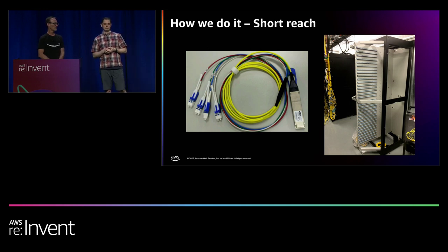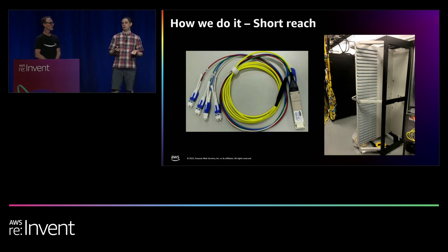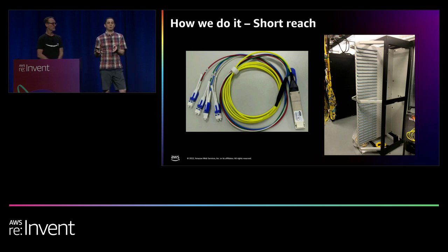gig instead. So the standard way of doing this is, like you see on the left, a breakout cable. You connect that to a patch rack at the side that's purely there to handle incoming connections. These patching racks are problematic for our data center folks. They're passive racks. They must be located directly beside the routers, but they're passive. So that means there's no power coming in, and therefore there's no heat going out. It's not great for thermal management when you think of the rack beside it of routers may be emitting 40 kilowatts of heat.